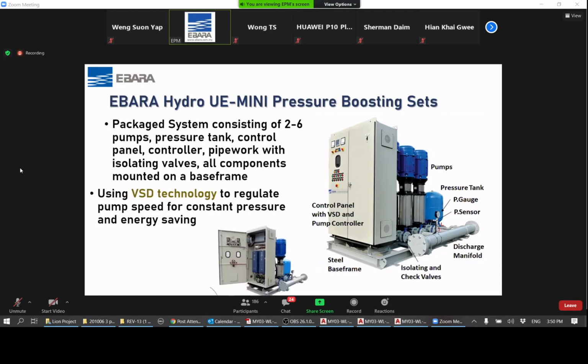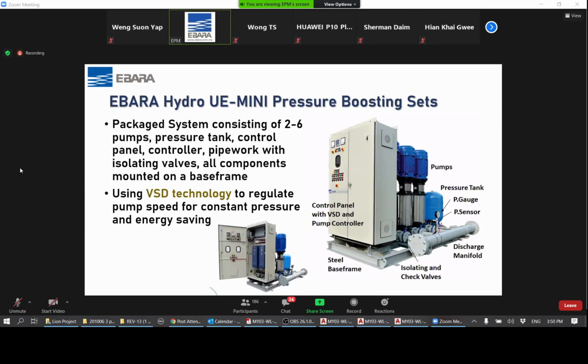A system like this also uses Ebara variable speed drive technology to regulate or control the pump speed to allow for a very constant pressure. Not only that, it also leads to very high energy savings due to the variable speed operation of the pump. When the pump reduces its speed, it actually saves a lot of energy, especially in conditions of low water demand.